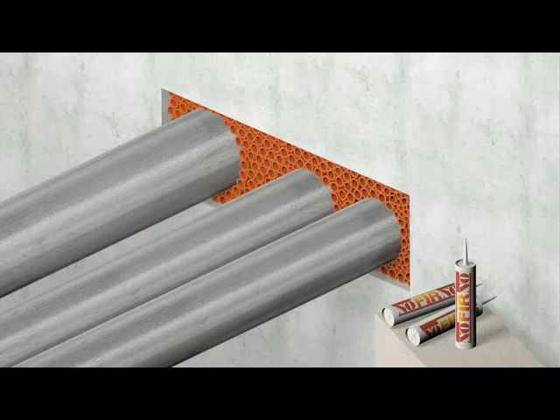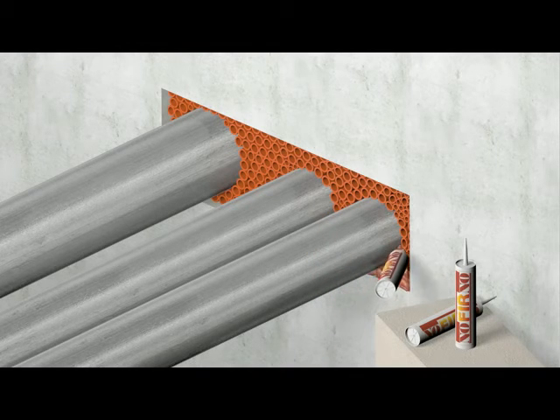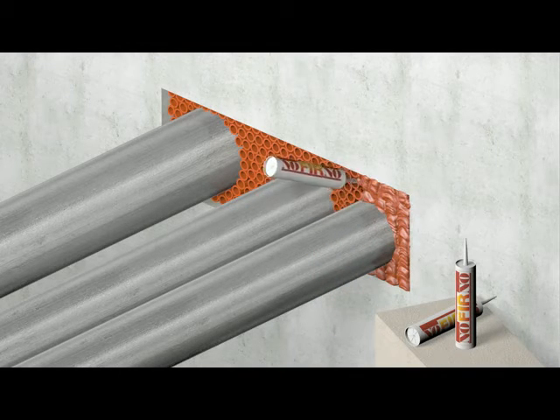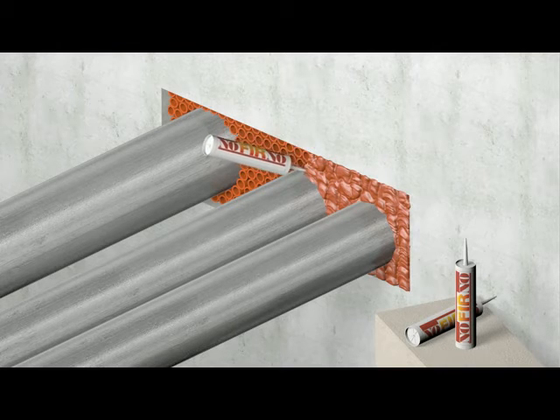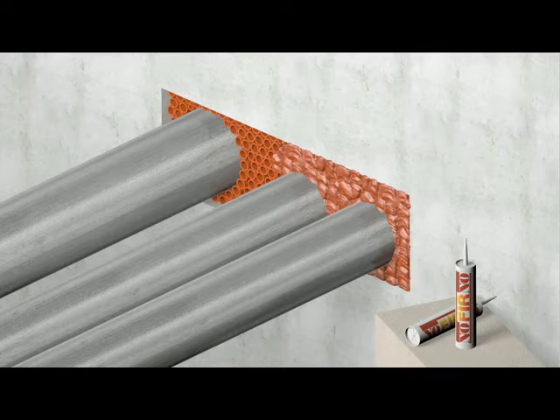A 20mm thick layer of Nofirno sealant is applied at each side of the conduit. When working on larger conduits like these, the sealant should be applied in two or more parts. Due to the fast curing of the top layer of the sealant, the amount of sealant should not be more than can be finished within 10 minutes.